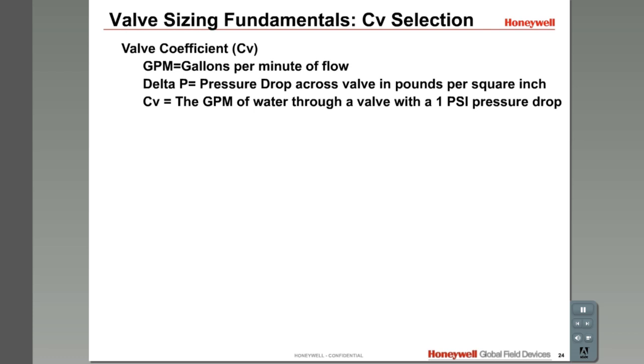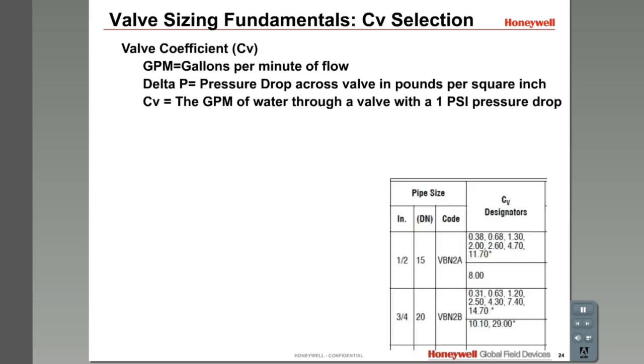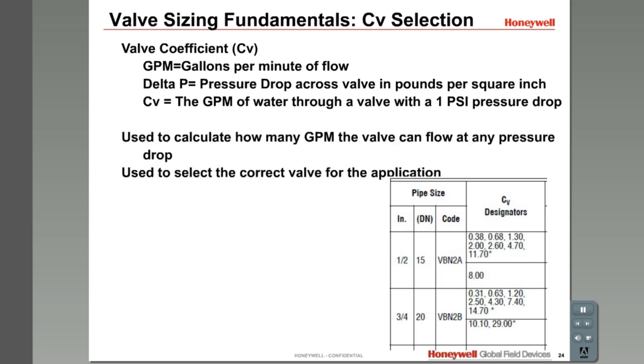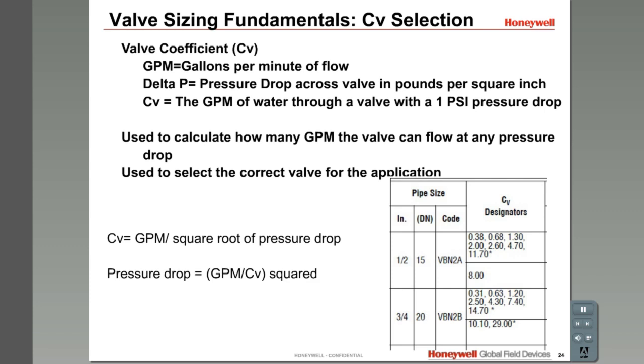per square inch. As you can see in the chart, a valve of a certain size, say a ½ inch, is available in more than one CV. The valves with the higher CV have less resistance to pressure, or pressure drop, than the ones with a lower CV. This is critical in selecting the right valve.